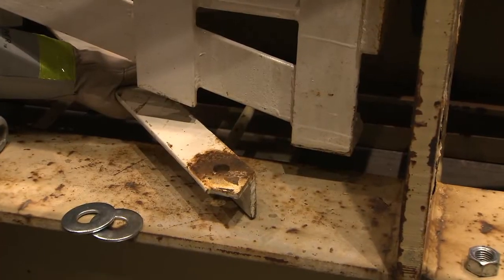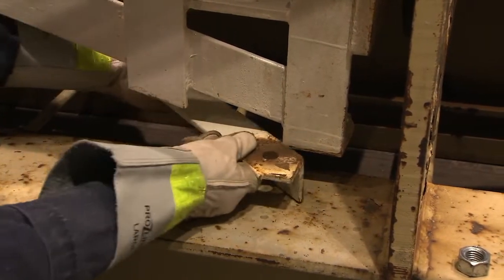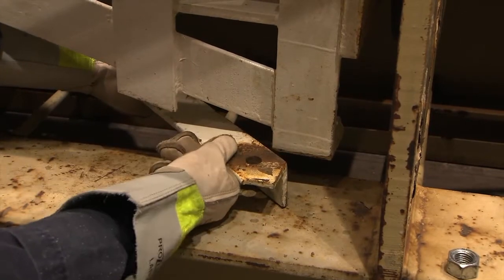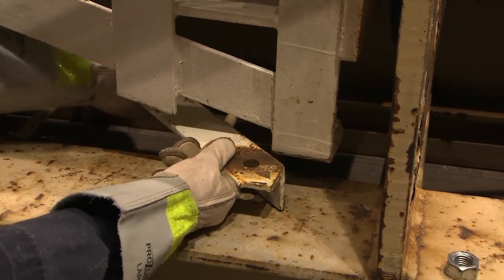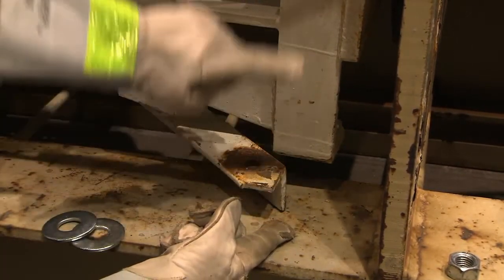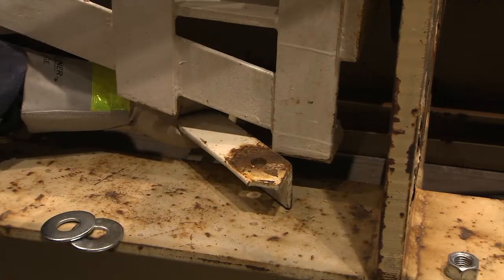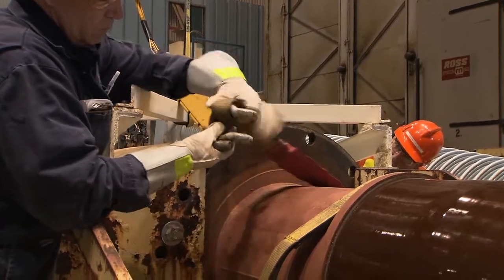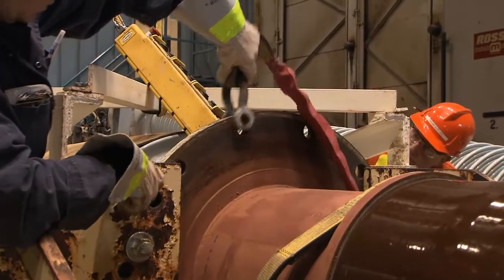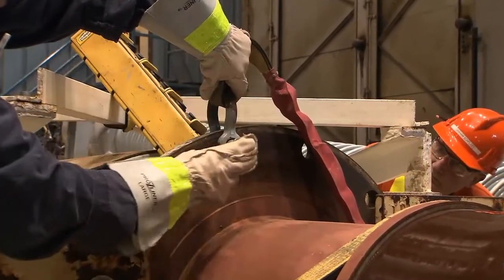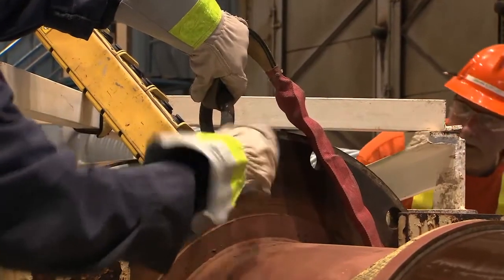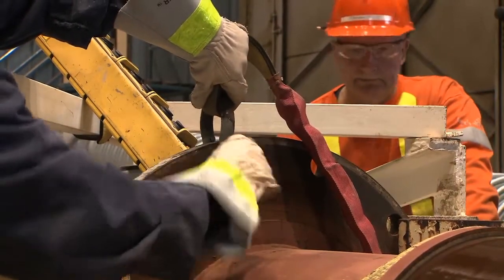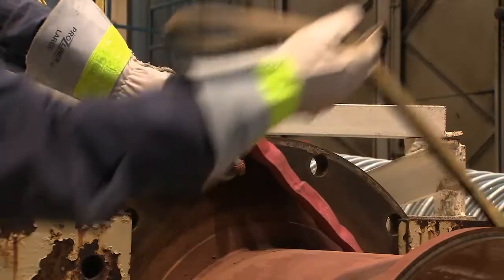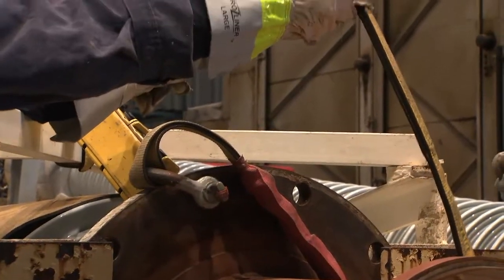In some situations, and depending on how much space there is under the bushing, it may not be possible to slide the crossmember under the jig to be able to attach it. In this case, it is necessary to raise the bushing using 2 slings that are attached to the flange's separate shackles. These types of situations make it a necessity that the bushing team communicate well with each other and function with a high degree of astuteness and agility.